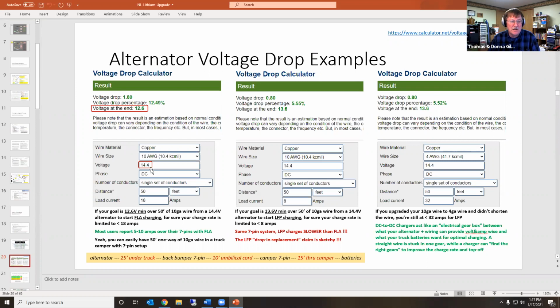What this was showing is, if you have an alternator putting out 14.4 volts, and let's say your wire is 50 feet in length, and you try to put an 18 amp load on that wire, your voltage is going to drop down to 12.6 volts. That's the bare bones you need to start lead acid charging. So this is a simple way of saying, for sure, if you have an alternator like this and this amount of wire, there's no way you can exceed 18 amps worth of charging with a flooded lead acid battery.